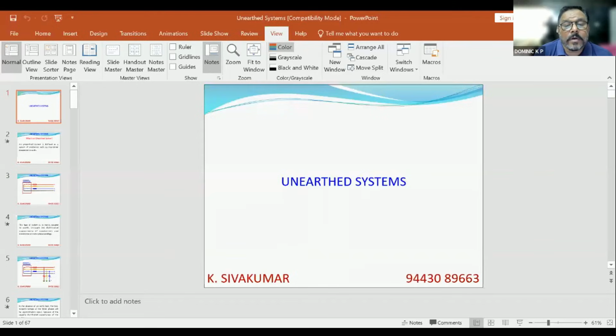Sir, this question I have to read out very slowly so that you understand. The question from Nandu Gopal. For a hospital operation room, we are supposed to follow IT system. Then won't transient over voltage be really dangerous? Then does the high impedance earthing which is done on the load side reduce this? I'll repeat this question. For the hospital operation room, we are supposed to follow IT system. Then won't transient over voltage be really dangerous? Then does the high impedance earthing which is done on the load side reduce this?